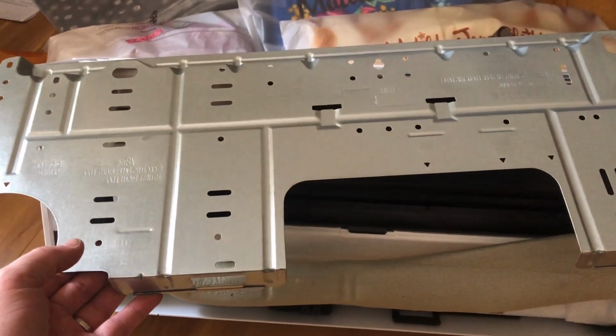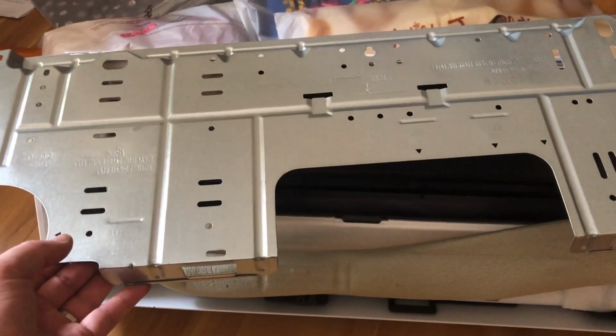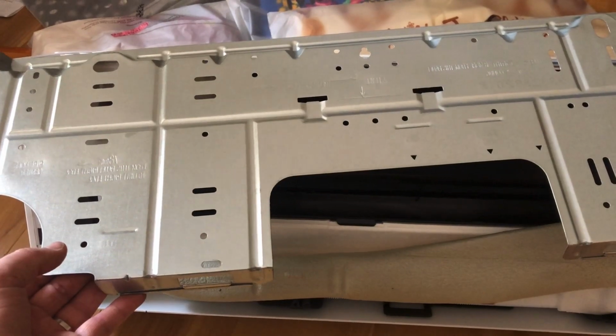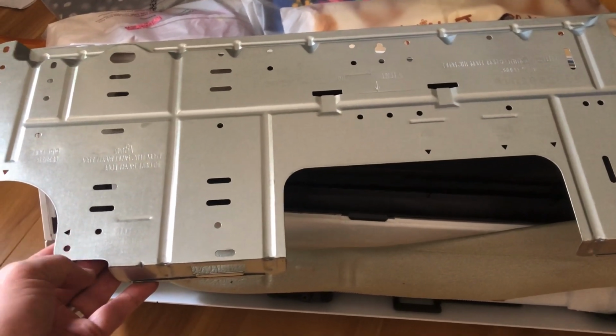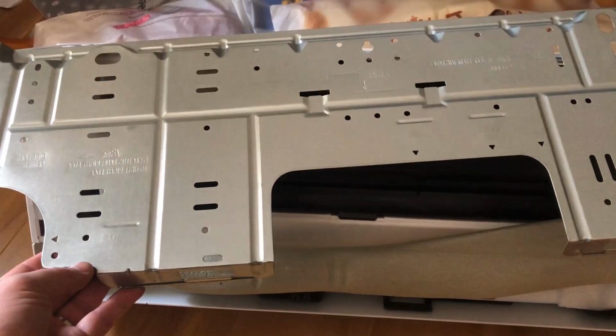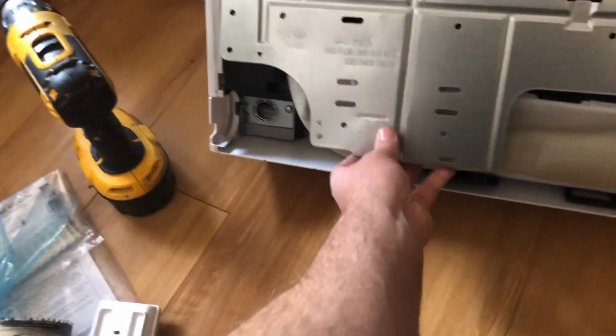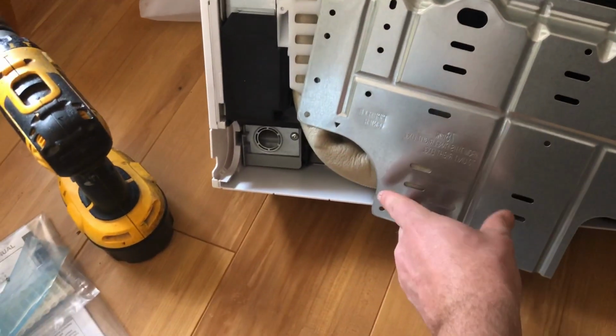If it's not perfectly level, the condensation will not drain properly out of this unit, so this is very important. We're going to mount this and make sure we hit studs using the various holes. The other important thing is right here, off to this side, is where your 2.5-inch hole is going to get drilled.